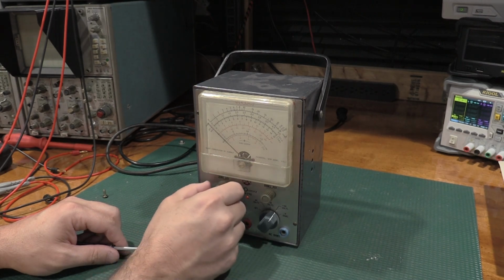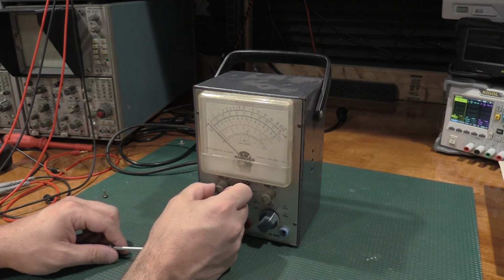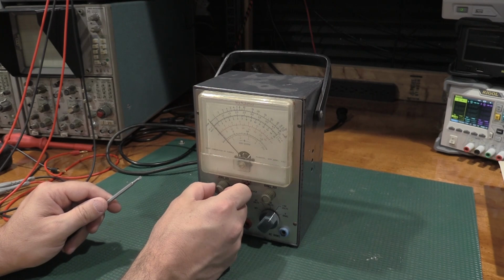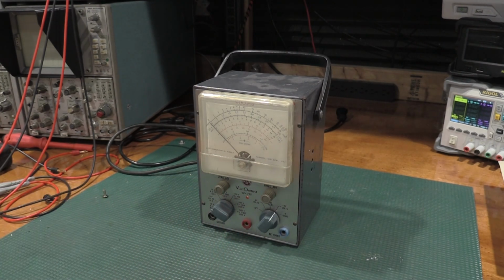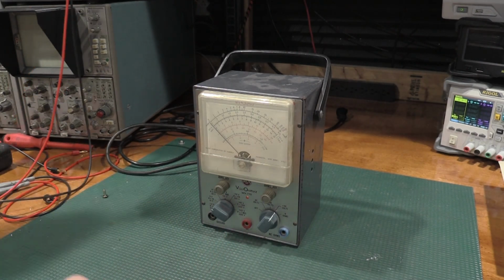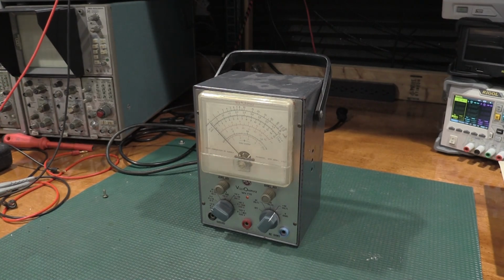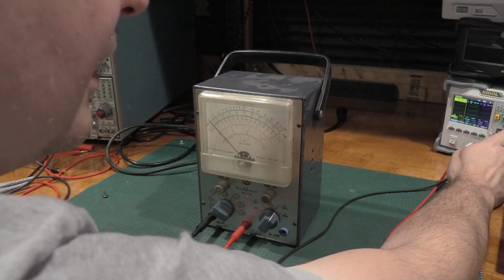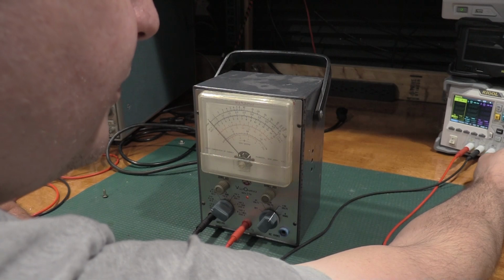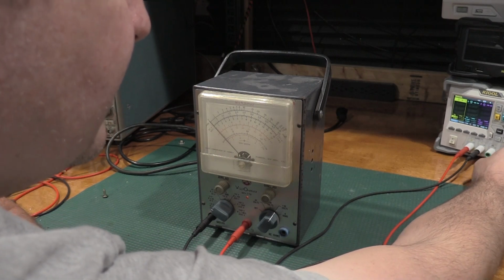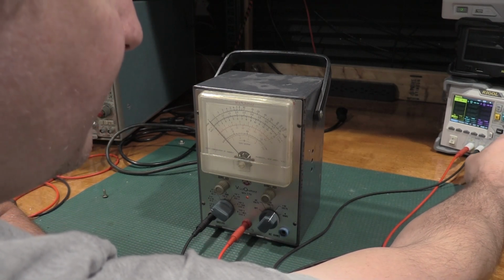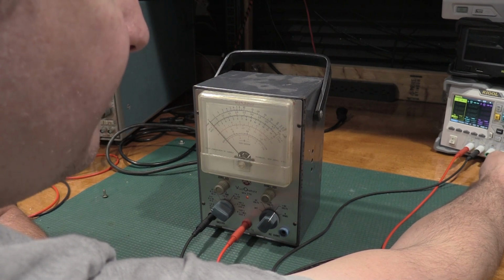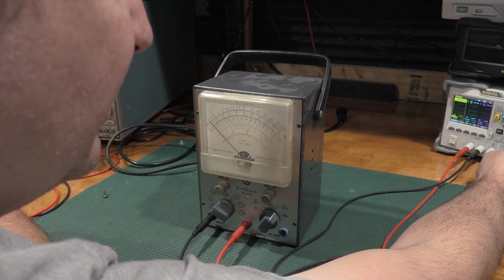Now we're coming to rest a little too low, so I need to zero set, because we mechanically zero set the meter. Now I need to zero set the bridge, which is there. Now I just need a couple of probe leads. All right, we're going to set this to 4 volts, because I want a decent deflection, but I don't want full-scale deflection. And we're going to set for 5 milliamp.